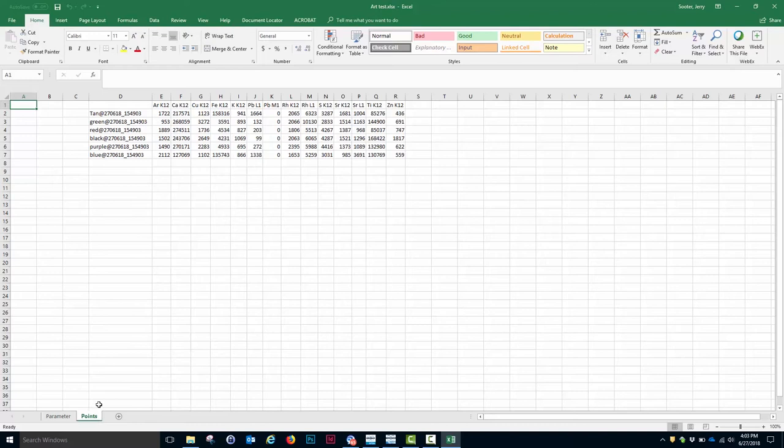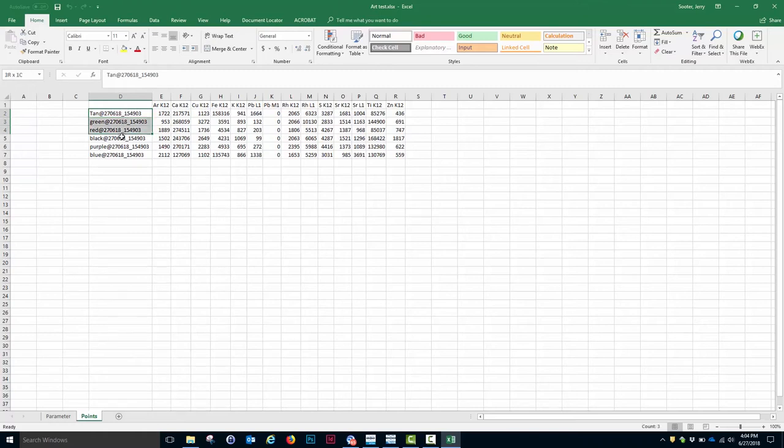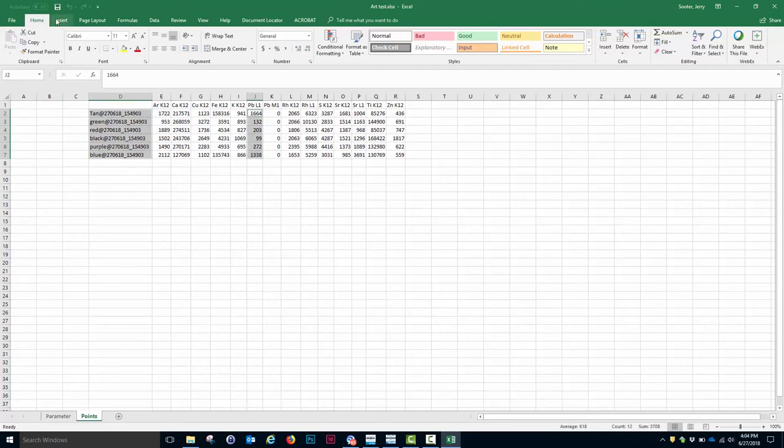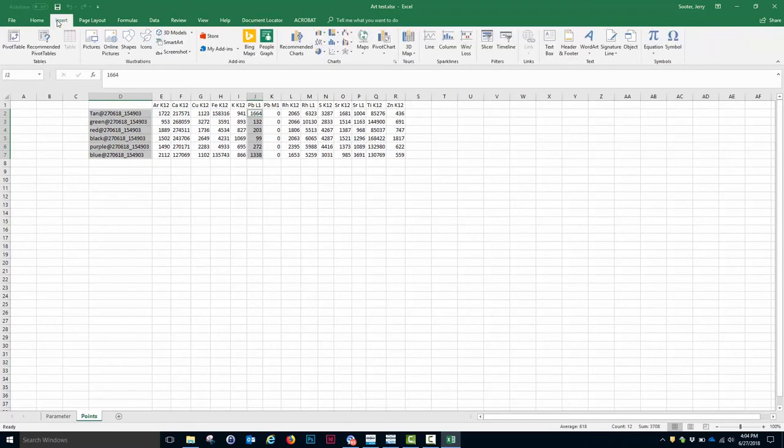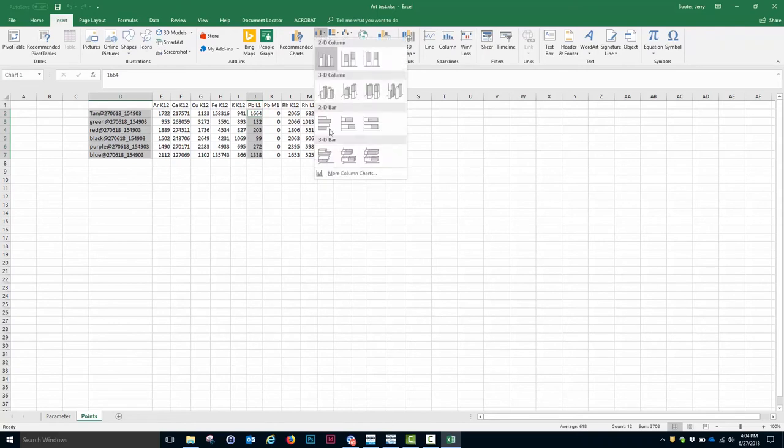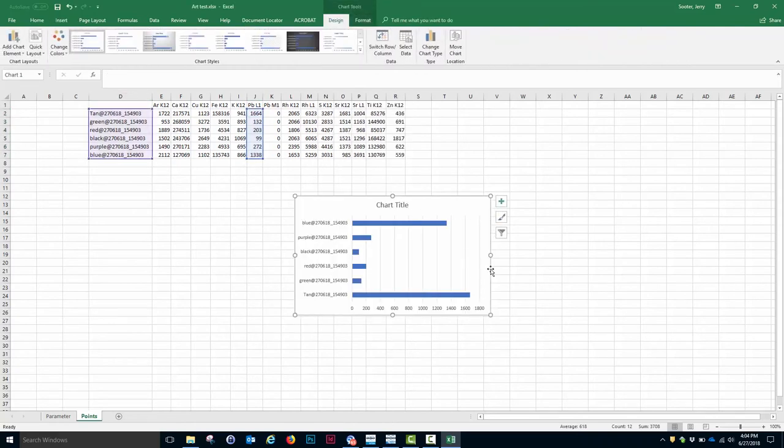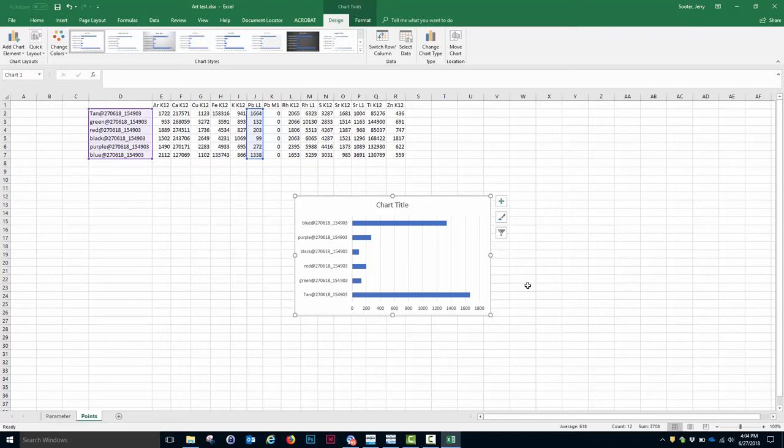I can then take this data and manipulate it in many different ways. For example, if I take the intensity column or the name column and select it and the lead intensity column and select that, I can then insert a bar graph, which shows me the net intensity of the lead in each of the various colors. This clearly shows that the tan color on my painting has the most lead. The blue color has substantial lead, but the other four colors have relatively little lead. You can do any Excel manipulation you like with Excel and the data. For example, one semi-quantitative measure used in many cases is the ratio of the various intensities in these spectra.